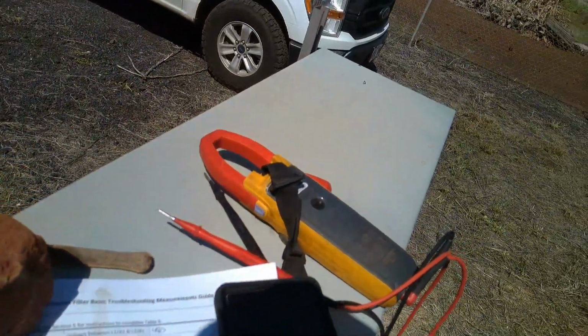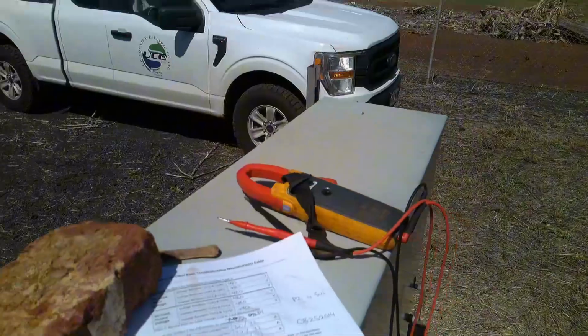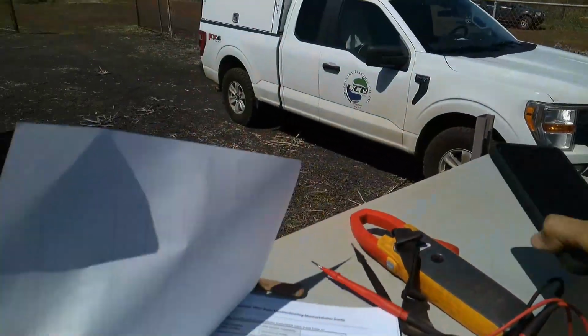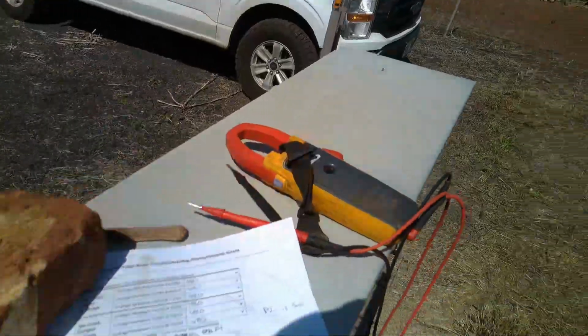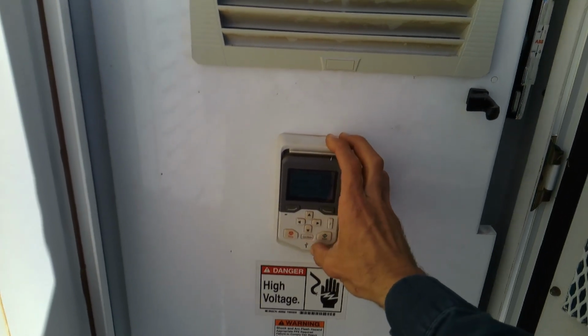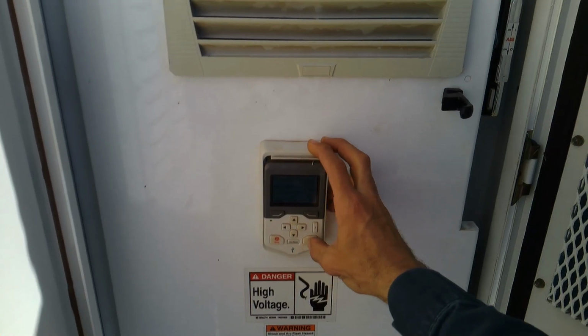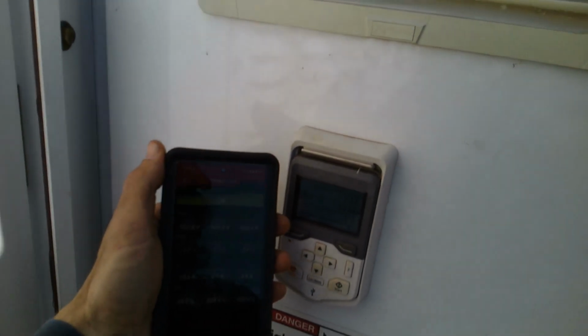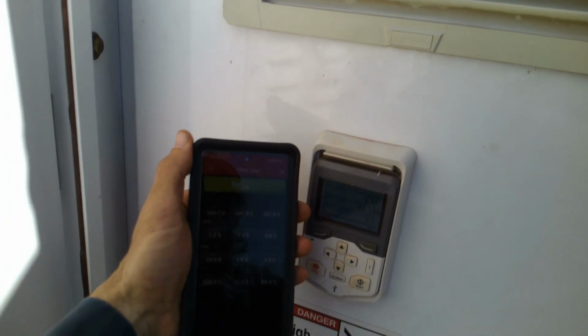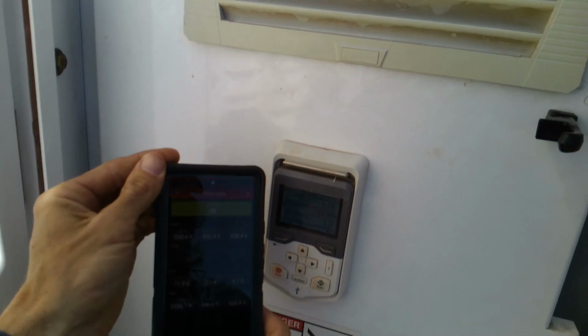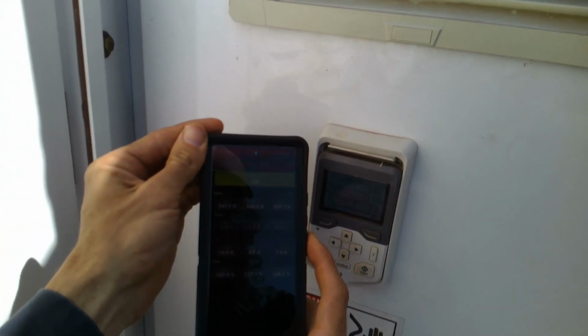Okay, we're gonna give it a shot, see if the fault occurs. I can just hold this in my hand. We're looking for these currents and percentages, these voltages, and the tuned circuit current loaded. And we can track the VFD output during all of that. So for this test, I'm just going to run this bad boy in local. There we go. It does a very slow ramp. There we go. Whoa, there goes the voltage. You can see the voltage climbing there. 525 at 3 hertz, 550, 550, 14 amps.